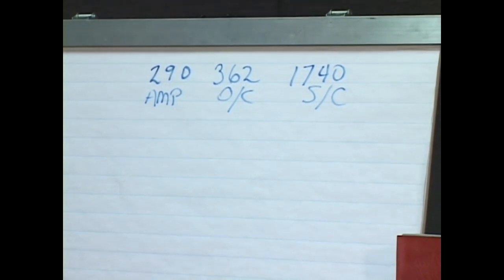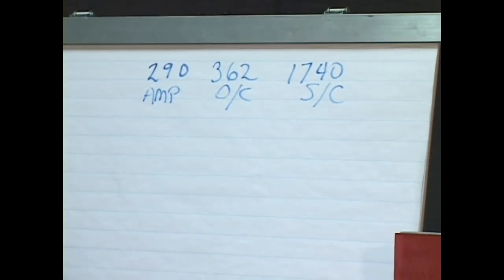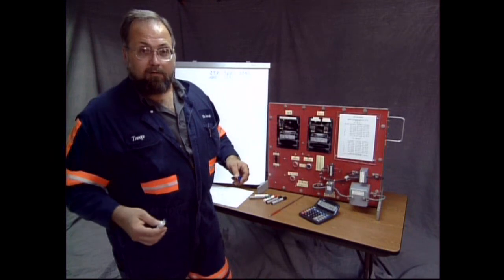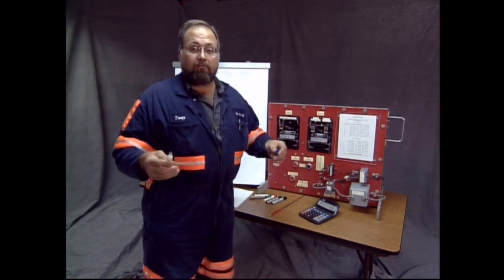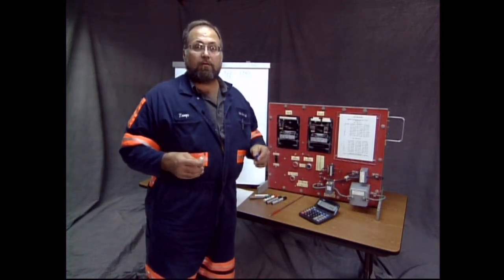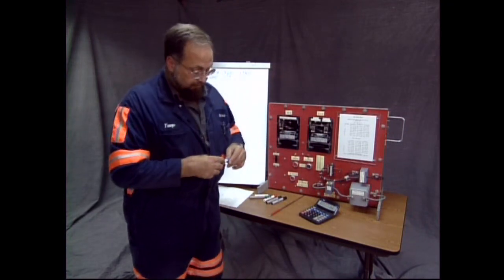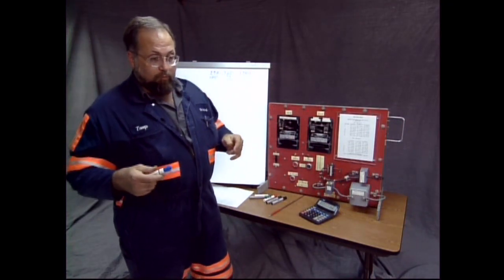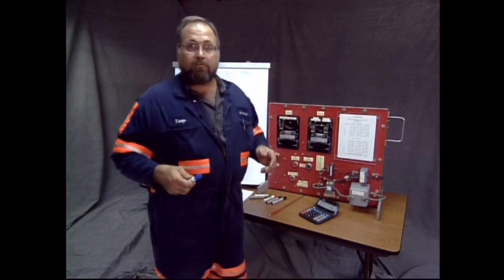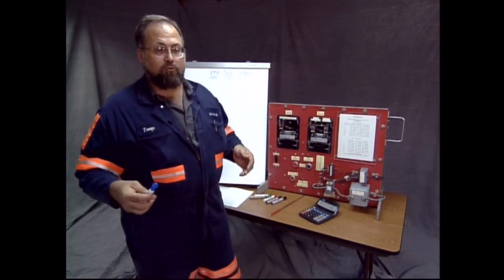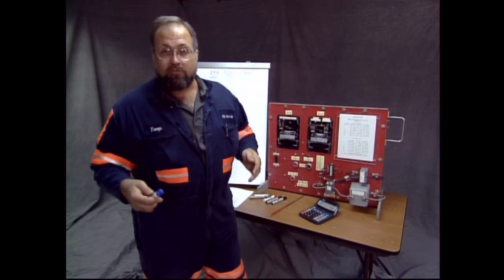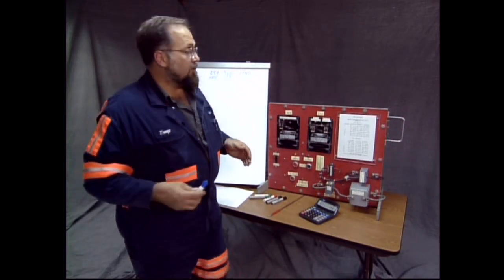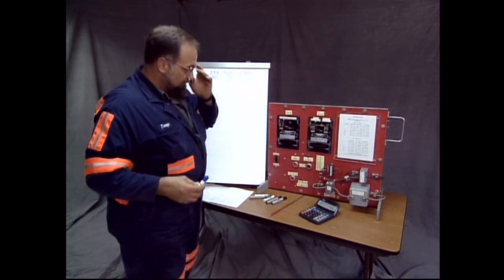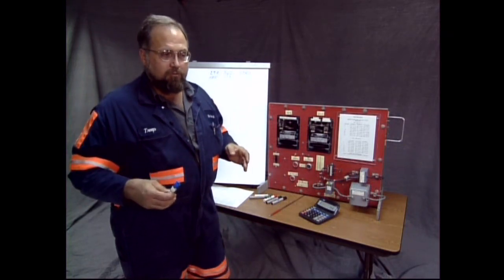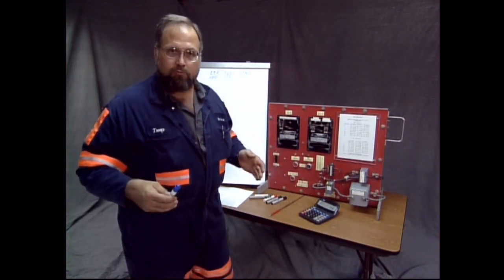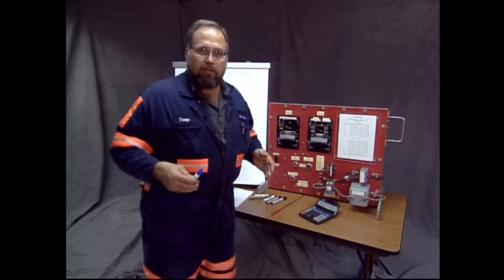Now guys, these are our maximum levels. This is not what you need to set on. This is the most elevated setting that you could possibly choose and remain legal. Now, myself, I'm more inclined to err on the side of the angels, to set at an adequate level, set to where you don't have nuisance tripping, but you don't want to challenge the maximum on these settings. Because let's face it, short circuit, when you adjust a short circuit, you're adjusting how big the fire will get if you have a short circuit, how large the event will be.